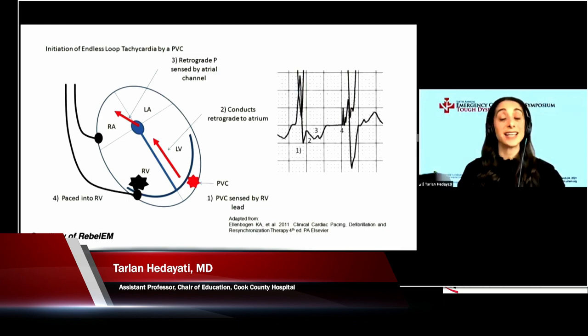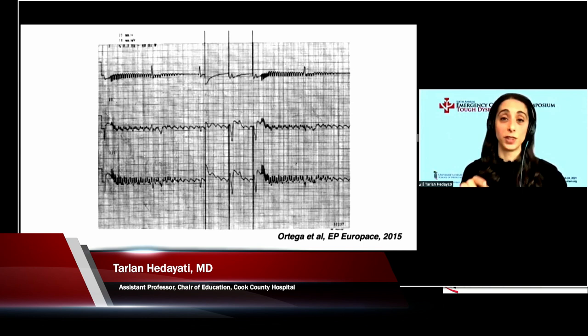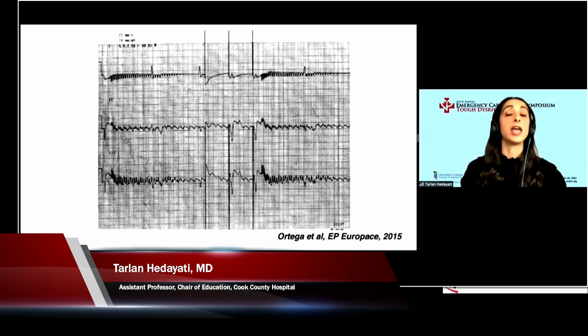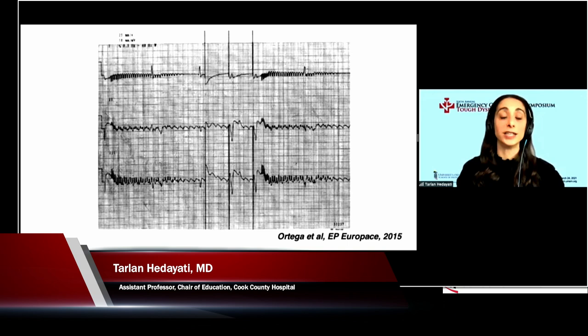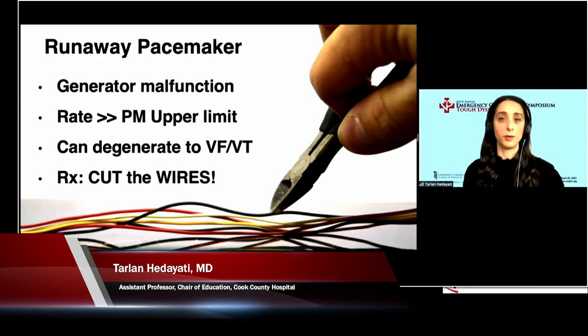This is an EKG that is used quite often, and it basically looks like V-fib when you take a look at this. This is a runaway pacemaker, where the pacemaker is just firing away willy-nilly. Unfortunately, the problem with runaway pacemaker is that this is a generator malfunction, and the rate can far exceed the pacemaker limit. We're talking about 200s, 300s beats per minute, and that is not sustainable.